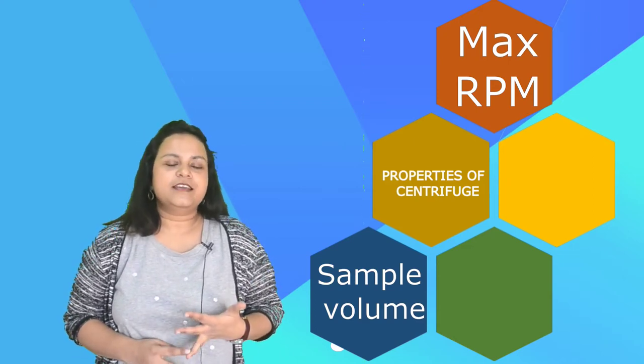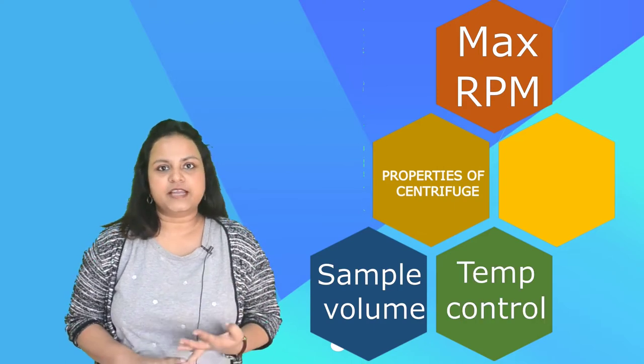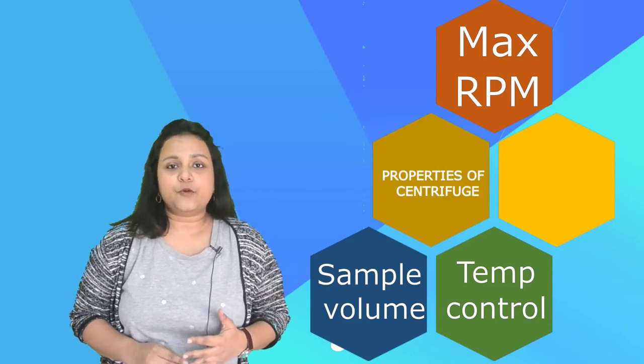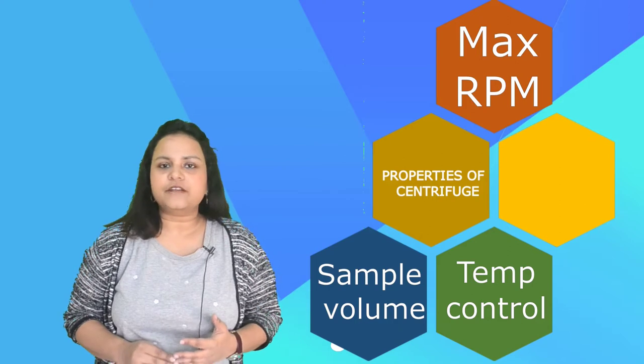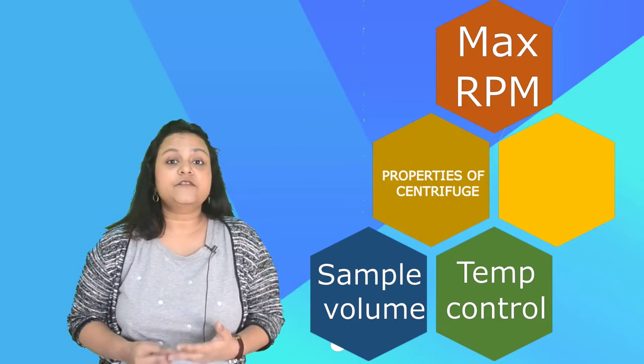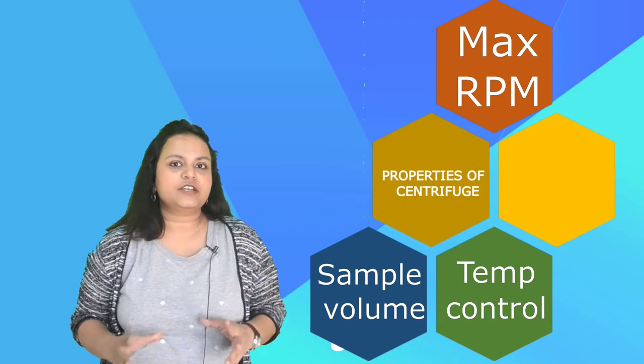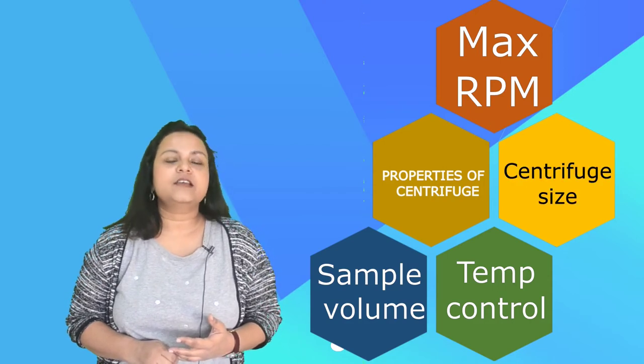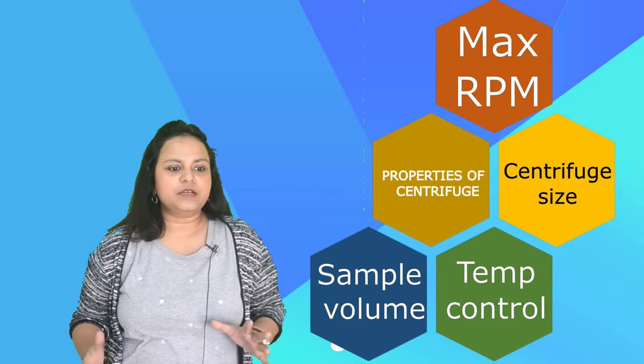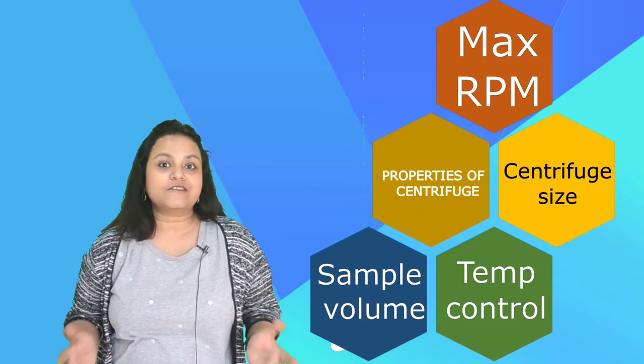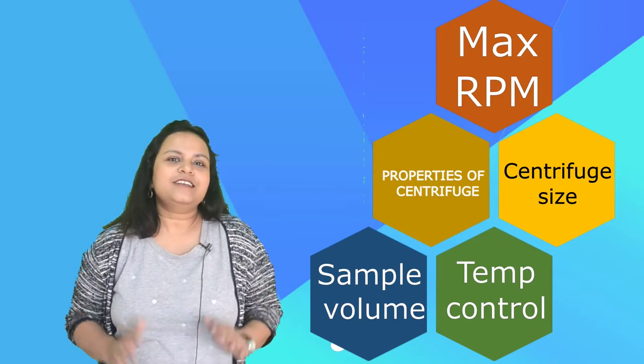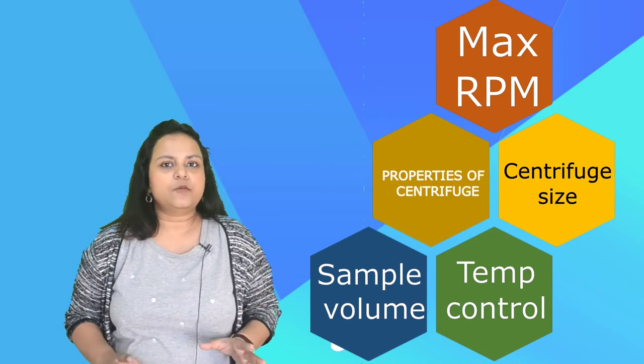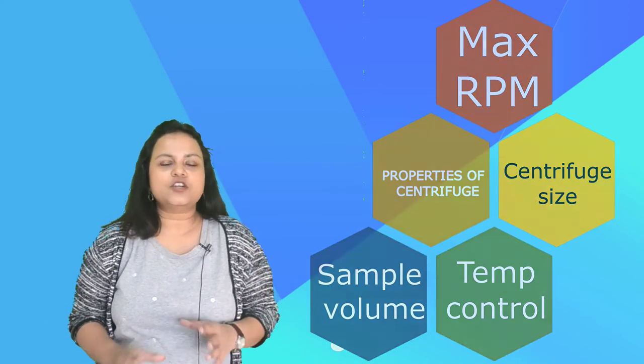The third property is whether there is an option for temperature regulation — that is, whether you can refrigerate your samples during the centrifugal run. This becomes very important if you are using biomacromolecules, because these molecules are often sensitive to higher temperatures and you would want a refrigerated rotor chamber while centrifuging. The fourth important property is the size of the centrifuge — whether it is a large bulky floor-type model installed in a central facility, or a small compact benchtop centrifuge that can be placed close to everybody's workspaces.